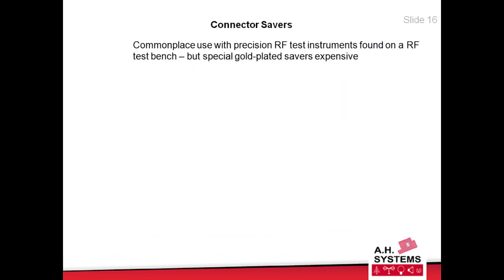Now, there's still something called connector savers. What's a connector saver? If you've got a very expensive instrument and you're doing a series of RF tests, like scattering parameters, that have to be extremely accurate, then rather than connecting directly onto the connectors on the front panel of that expensive test instrument, they provide you with, at a good cost, special gold-plated savers.